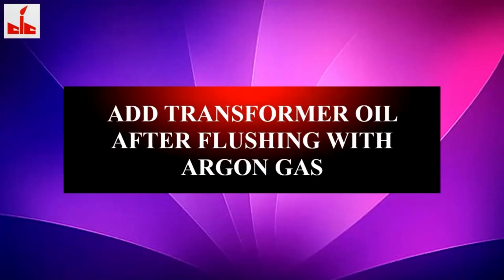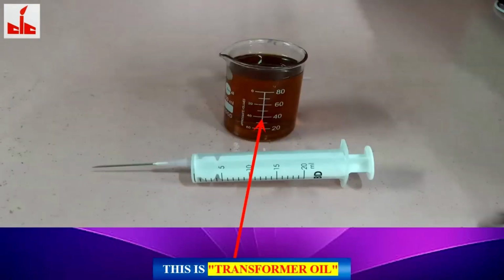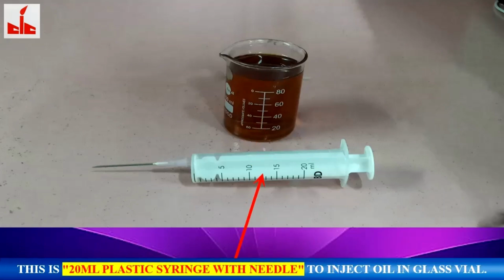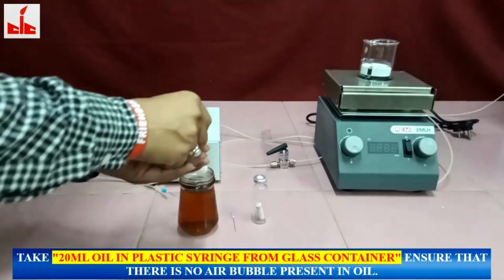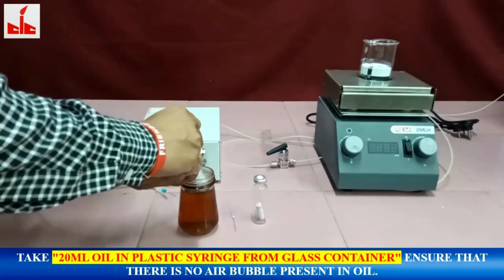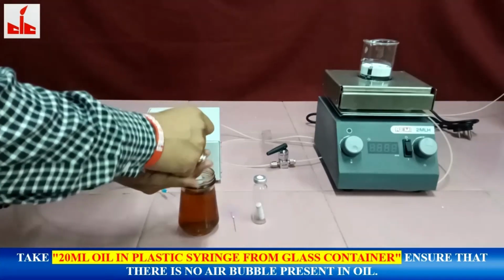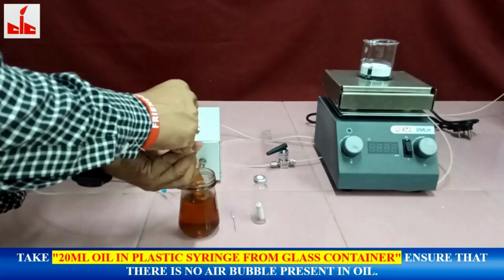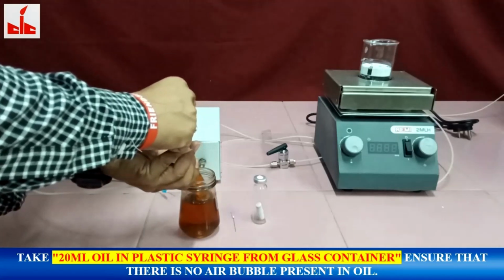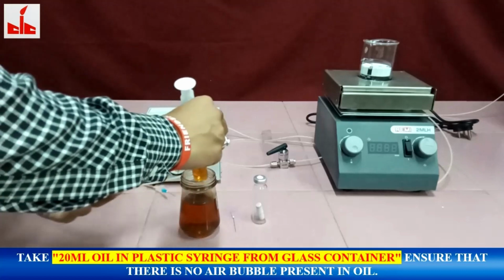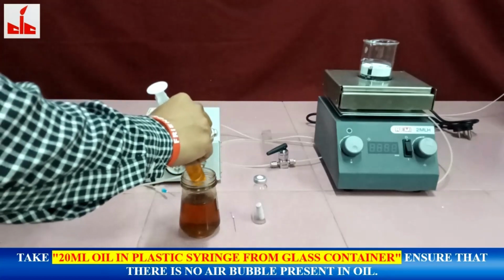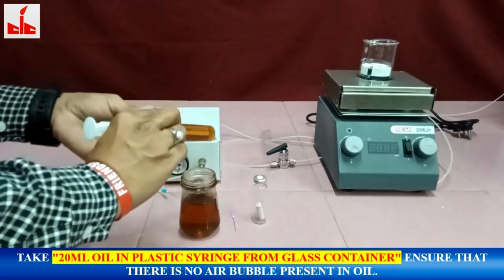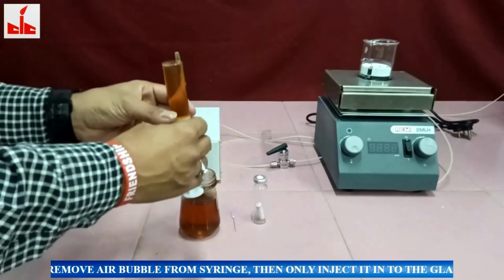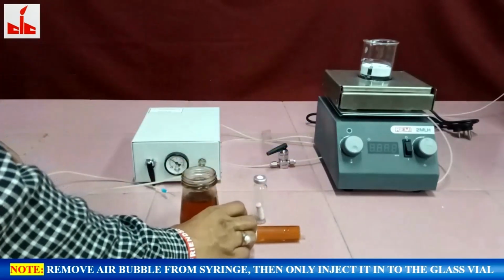Add transformer oil after flushing with argon gas. This is transformer oil. This is a 20 ml plastic syringe with needle to inject oil into the glass vial. Take 20 ml oil in the plastic syringe from the glass container. Ensure that there is no air bubble present in the oil. Remove air bubbles from the syringe, then only inject it into the glass vial.